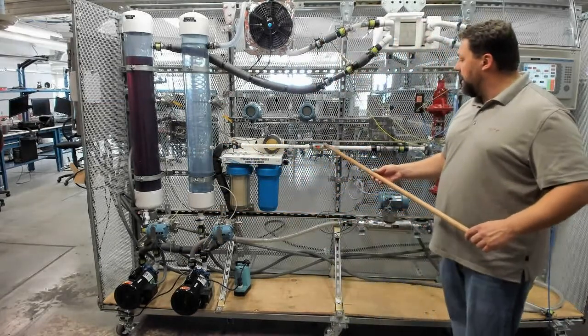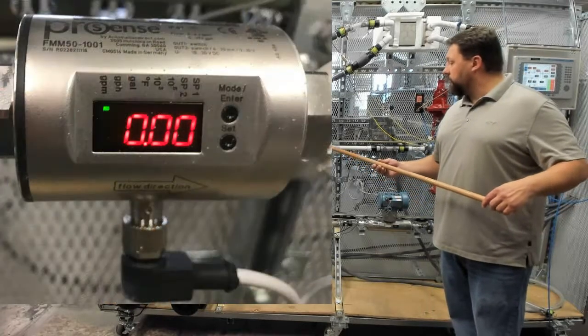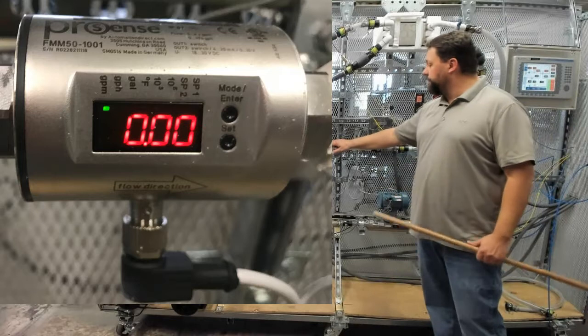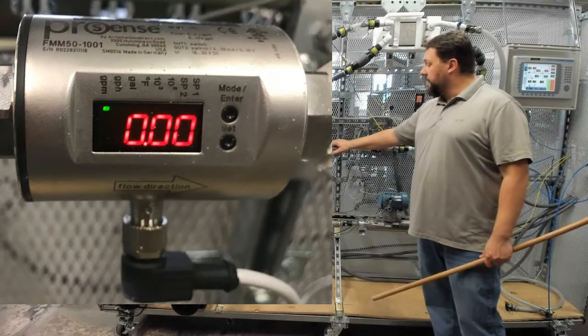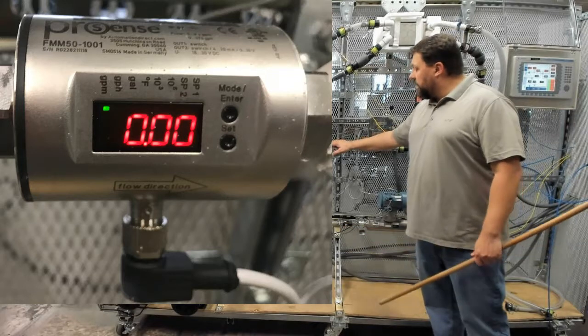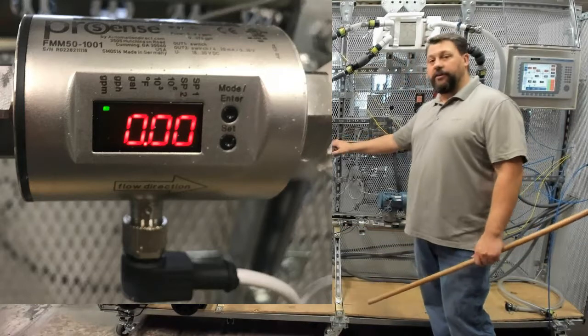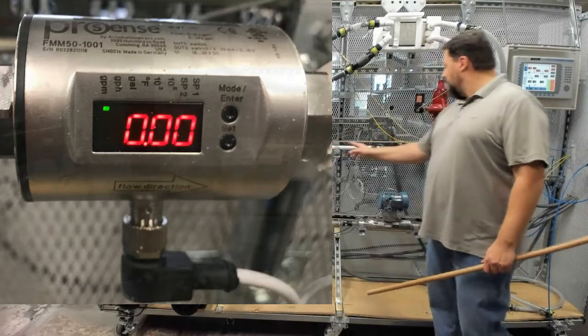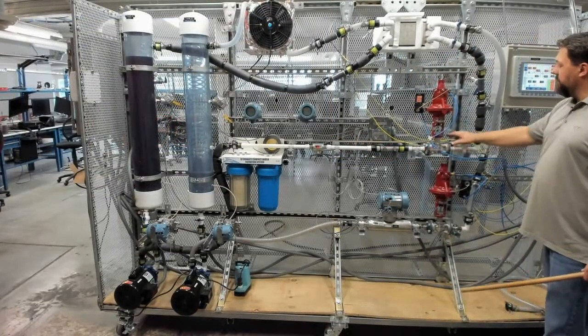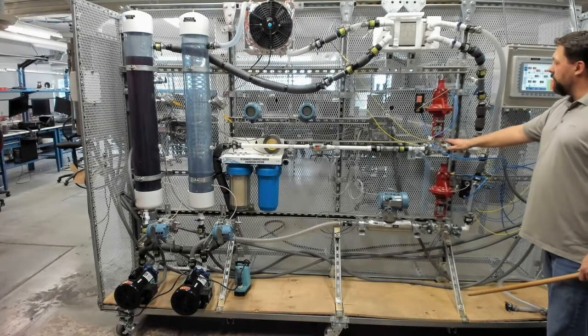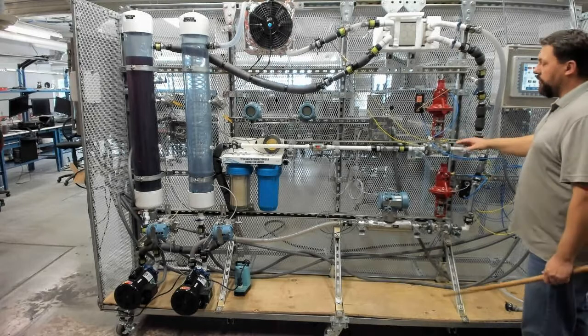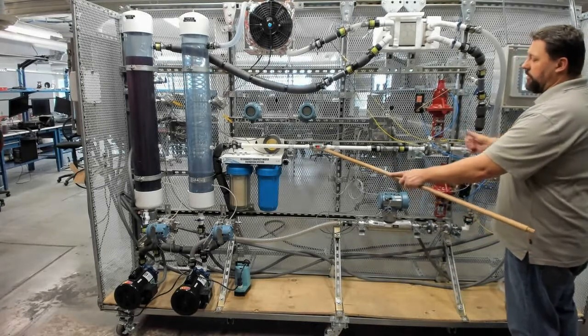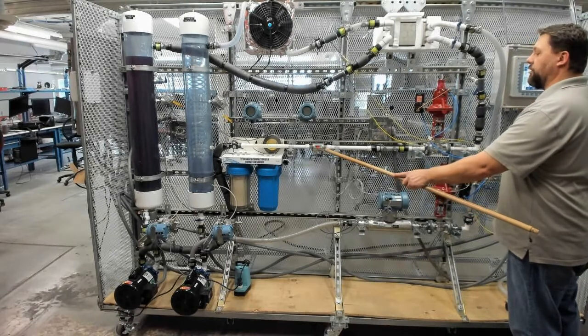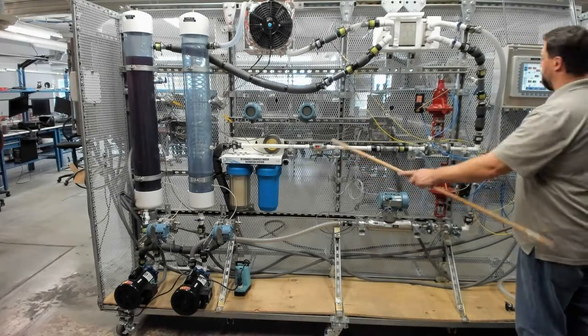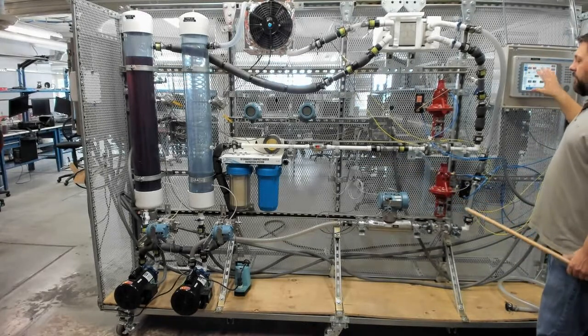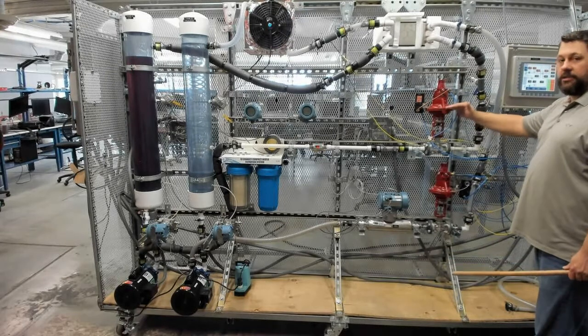And so we're going to come out of that system, and we come up over here. We come across, and we have a flow transmitter right here. This is the flow transmitter for the hot tank A. And this is monitoring how many gallons per minute. It could be configured for different units of measure, but that's what it's set up for right now. And then we come through this, and we come into a pneumatically actuated flow control valve. So this device sends a signal to the programmable logic controller. The programmable logic controller compares that measurement with the set point that we've set here and will adjust this while it's in automatic mode.